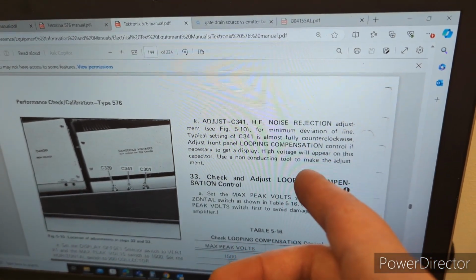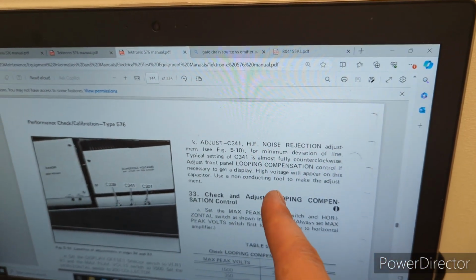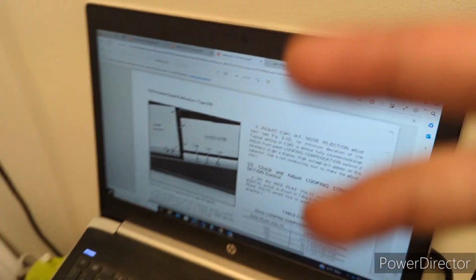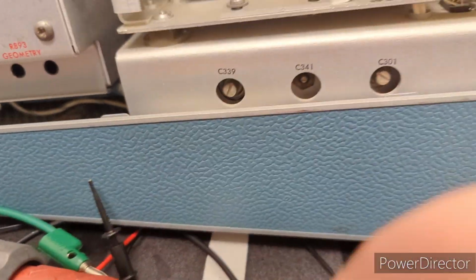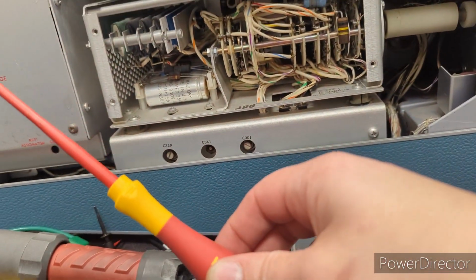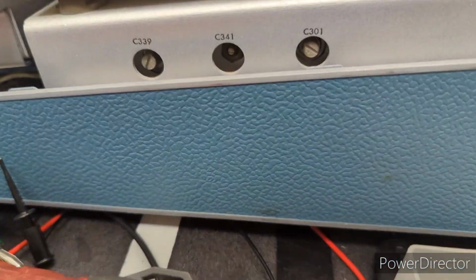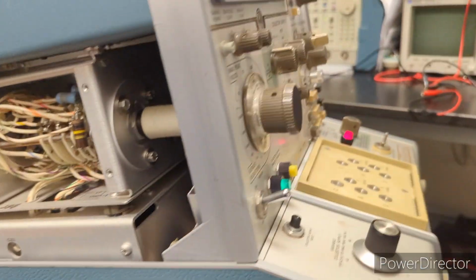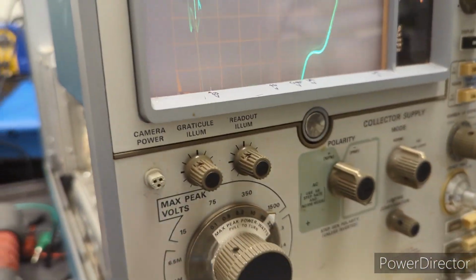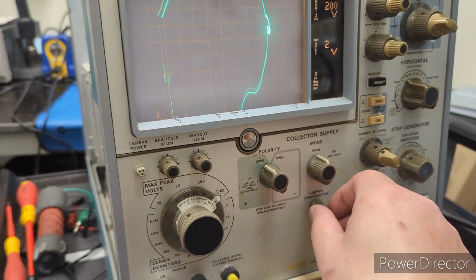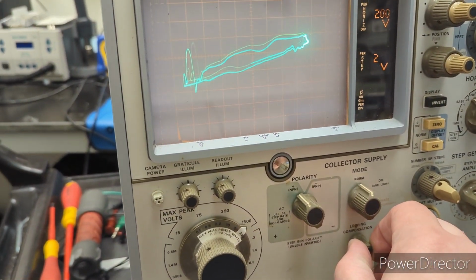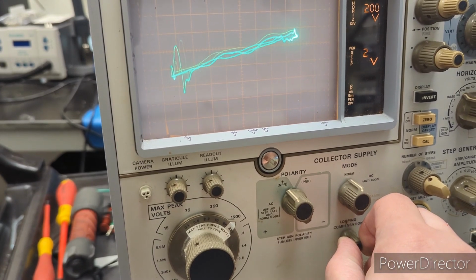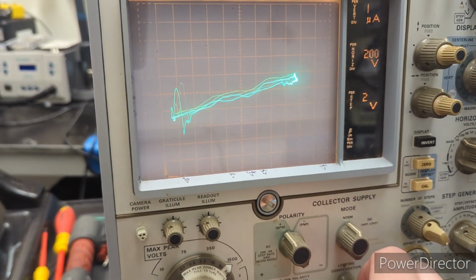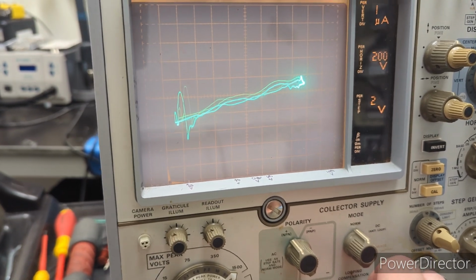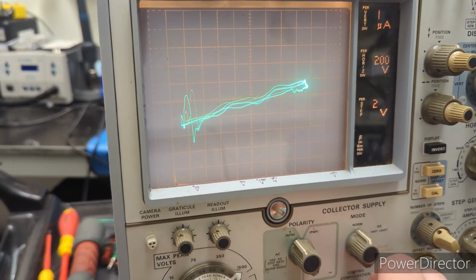It also adds that high voltage will appear on this capacitor, so be careful when you're adjusting C341. Again, I use my insulated screwdrivers to make these adjustments. So that one is turned fully counterclockwise. Adjusting the loop compensation on the front. Oh, well, there you go. Okay. So that brought that way down.